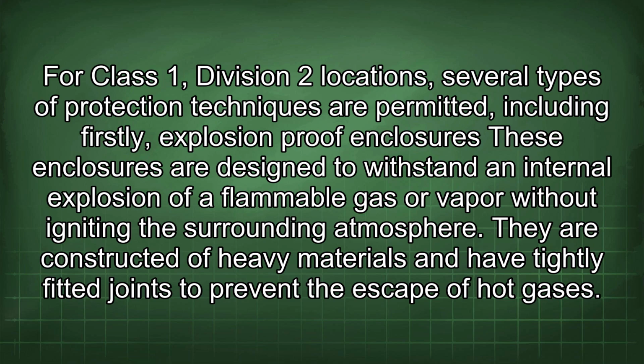For Class 1, Division 2 locations, several types of protection techniques are permitted, including, firstly, explosion-proof enclosures. These enclosures are designed to withstand an internal explosion of a flammable gas or vapor without igniting the surrounding atmosphere. They are constructed of heavy materials and have tightly fitted joints to prevent the escape of hot gases.